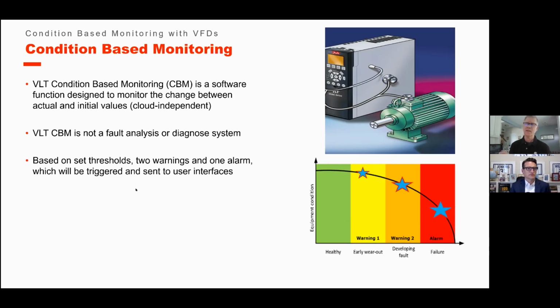So this is a baseline type of measurement where we want to measure all the great things that are going on in a machine while it's running in prime condition. And then we want to set our thresholds to say, when we get to this level, this is where we want to have notification so we can plan from there. So we get 2 warnings and 1 alarm. The 1 alarm will actually shut the machine down. So that's what you have to be careful of there.